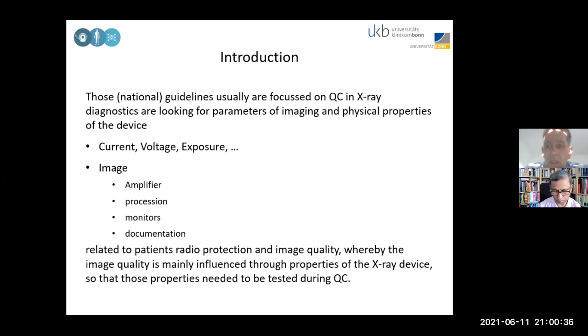There are some other parameters which influence the image quality. One is image processing, which is actually not related to the machine itself. It applies to the image which is already there, where you add filters, or manipulate it, or use lung windows or whatever. And the third thing is that you have to watch those images as well, so you need a screen. And those screens could have problems. If you don't have the right quality of screens, then maybe a good image is displayed as a worse image. So you see there is another part that needs to be quality assured: the monitor itself.